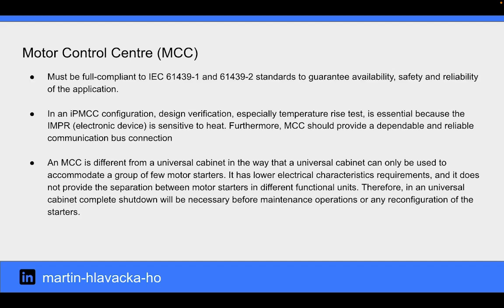MCC type assemblies must be fully compliant with IEC 61439-1 and 61439-2 standards to guarantee the availability, safety, and reliability of the application. In an IPMCC configuration, design verification, especially the temperature rise test, is essential because the IMPR is sensitive to heat. Furthermore, MCC should provide a dependable communication bus connection.